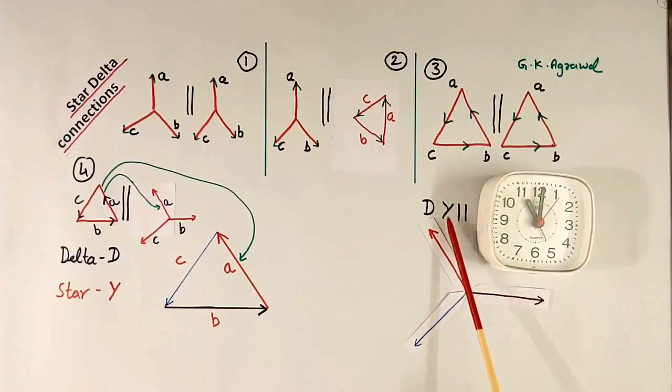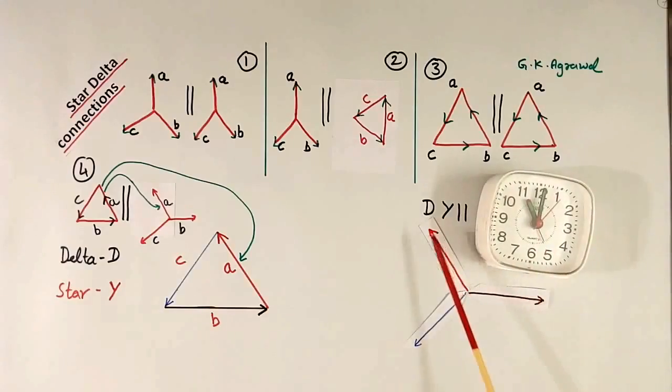This is secondary. So it is called Y 11. Secondary is Y 11 because phase A is towards 11. And we call this arrangement DY 11.